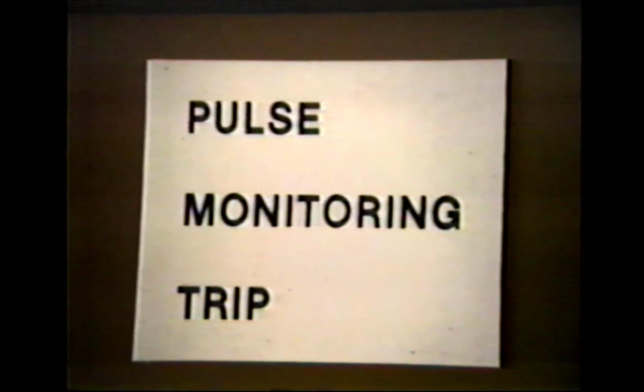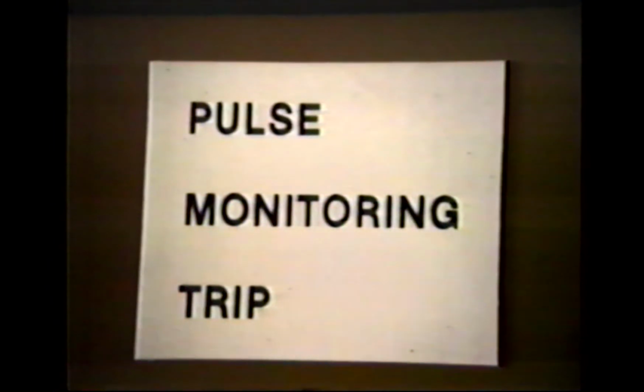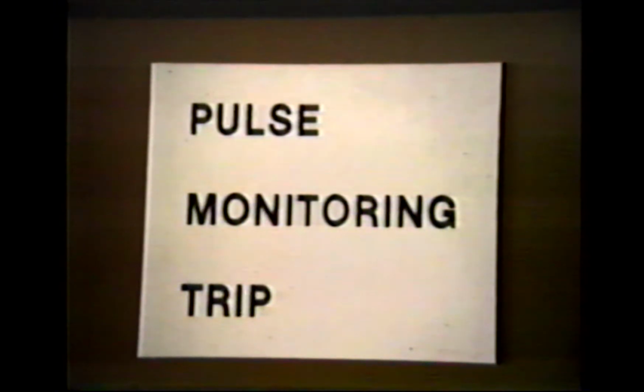The card's pulse monitoring trip circuit will not allow signals to be sent out to the PMTD or 1AD if a fault occurs that would cause a runaway truck. If the truck is in operation and one of these faults occurs, the PMT voltage will disappear and the forward or reverse contactor will drop out. Faults that would cause a PMT trip are a welded 1A contactor, a shorted 1-rec, or a faulty component in the turn-off circuit.